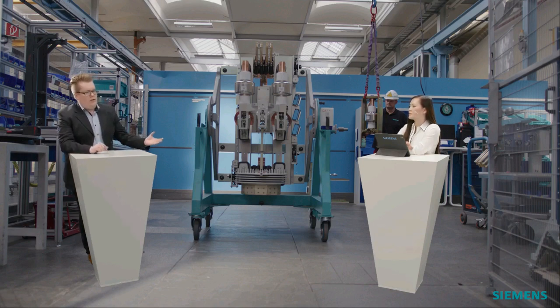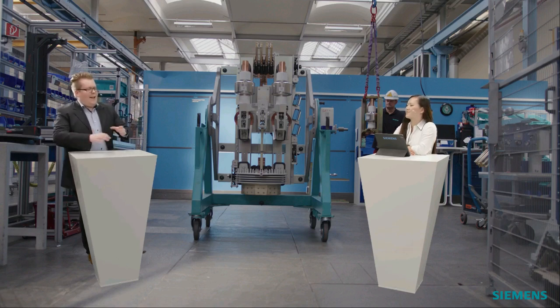What you can do, of course, which is not so quite useful, is to take this estimation tool for each generator and sum up all short circuit currents. But as I said, not really useful, and it's very important for a multiple generation feeder to consider really each branch, each generator branch.